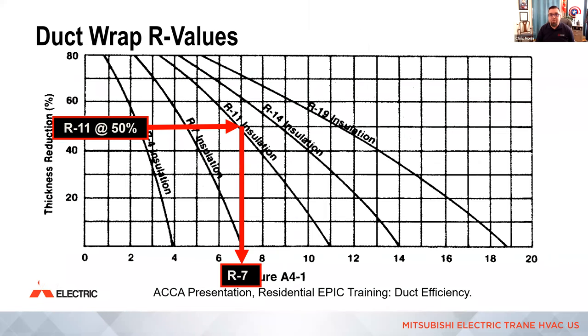It uses less electricity. If we compress insulation, right? Just 2% as an example here, 2% of air voids, and this is actually out of an ACCA presentation, could reduce the insulation value in half. So as an example here, the thickness is reduced just 50% of duct insulation, you can see we reduce an R11 down to R7. And that may not meet what the design was. We might have designed around R11 on the supply duct. And if we compress it too much because it's tight, or we're pushing down on that insulation because it goes into a bay or a ceiling or something like that, now we have R7 ductwork and it might not keep up for that space under typical demand days.